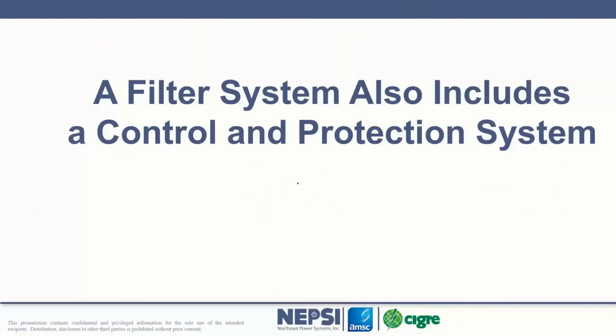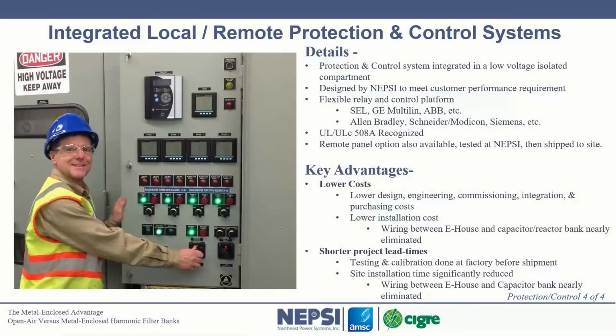So we are about done. I'm going to go through questions. Remember that we talked about L, R, and C. There's also voltage. There's also the control and protection system, which can get quite complicated. All harmonic filters have a control and protection system. Open air solutions typically have a separate device, oftentimes supplied by a different vendor. Metal enclosed solution is always part of the equipment. Of course, it's got advantages. Why? Because we're supplying that control and protection system.